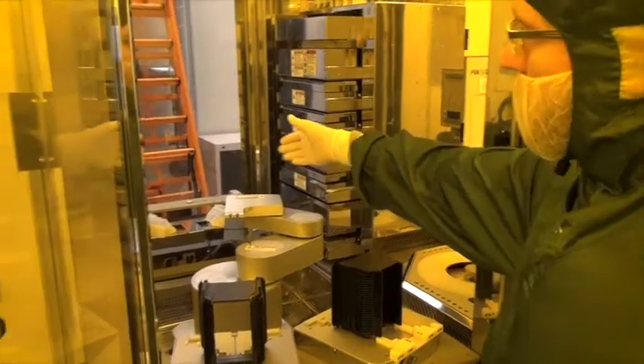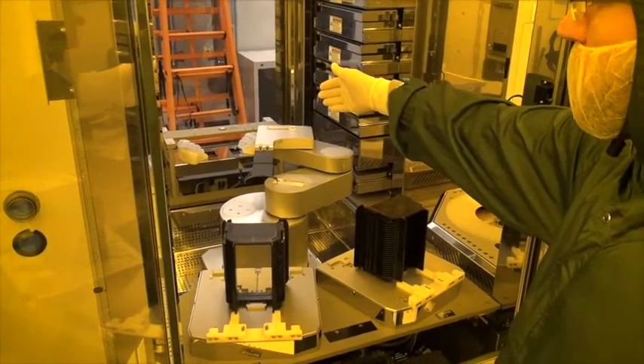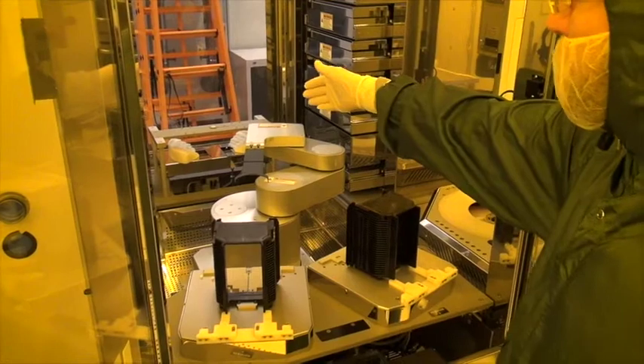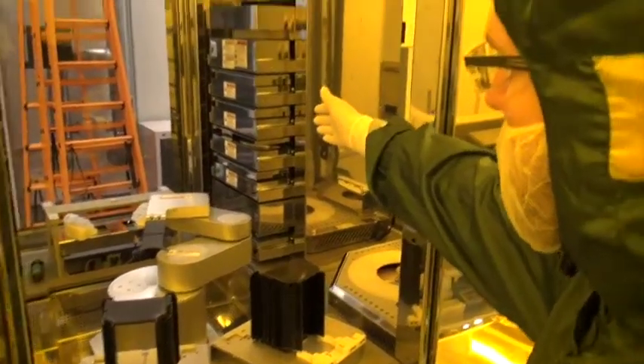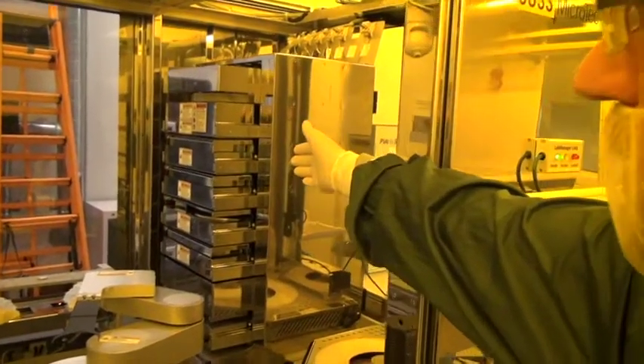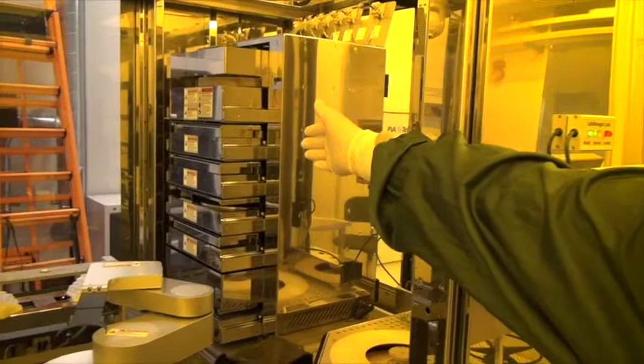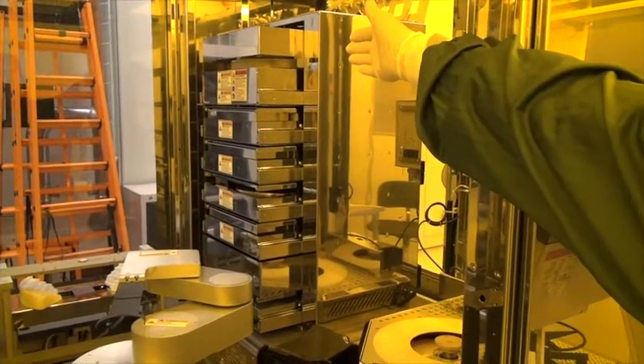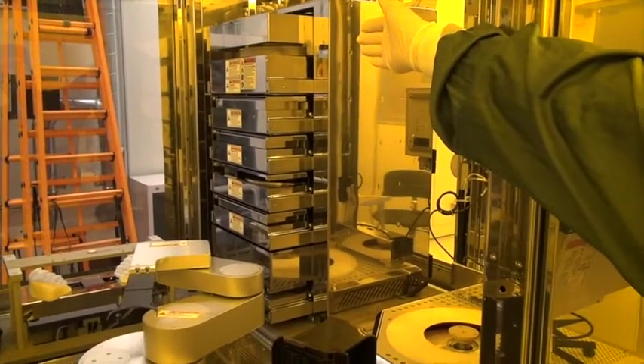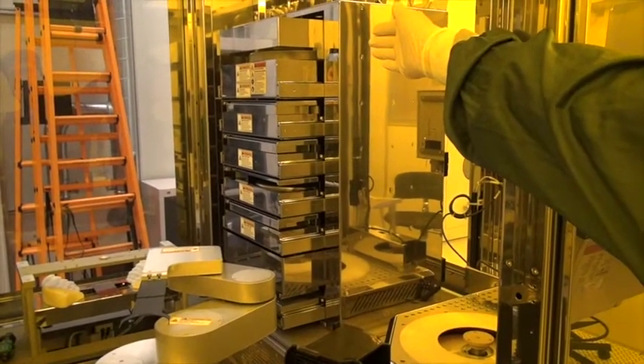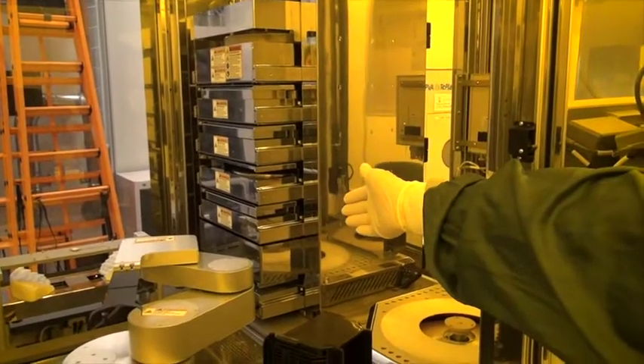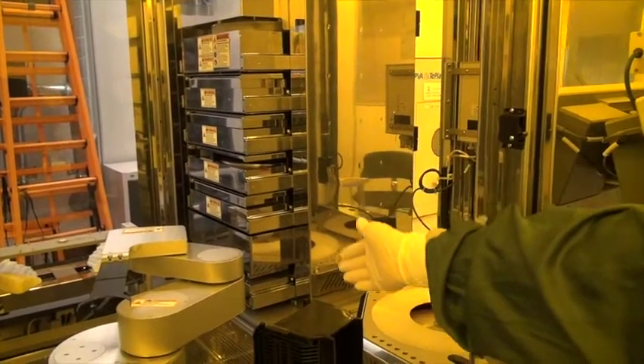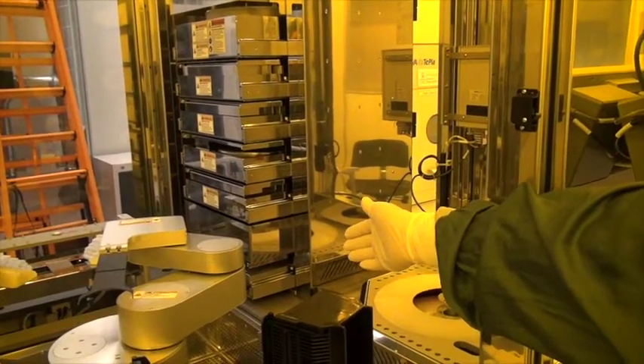In the back there is a wafer centering station and here to the right is the hot plate stack with a vapor prime oven for HMDS priming, four hot plates for soft baking, and at the bottom is a cool plate.